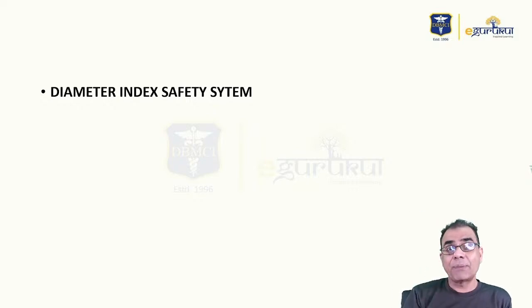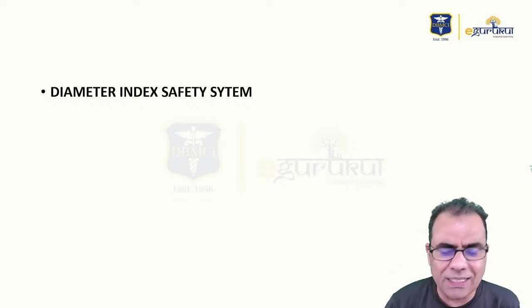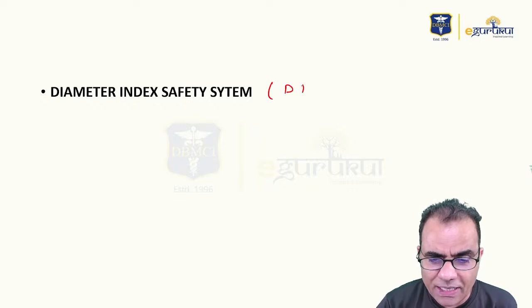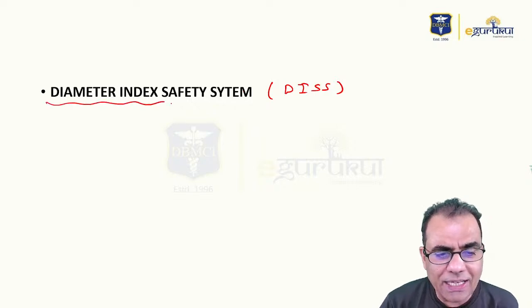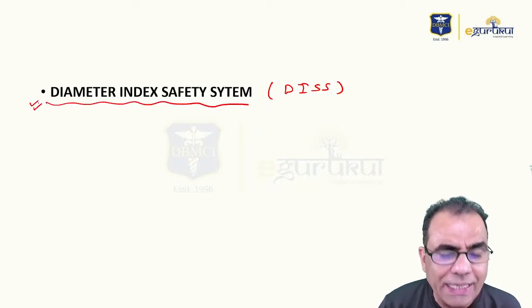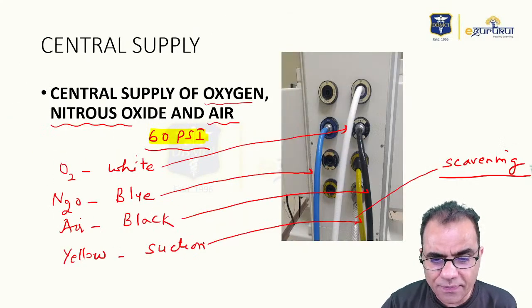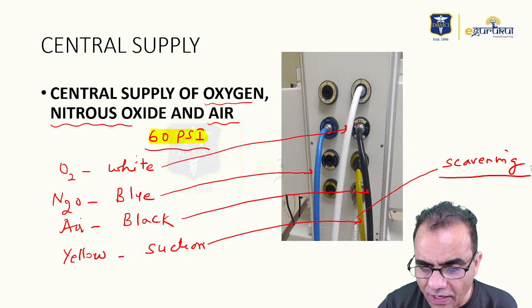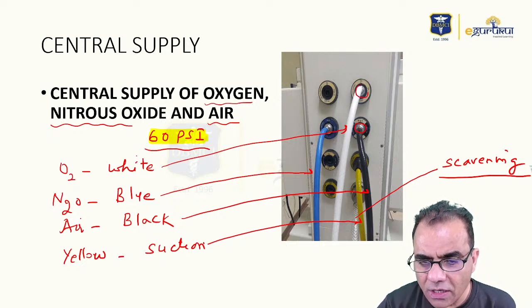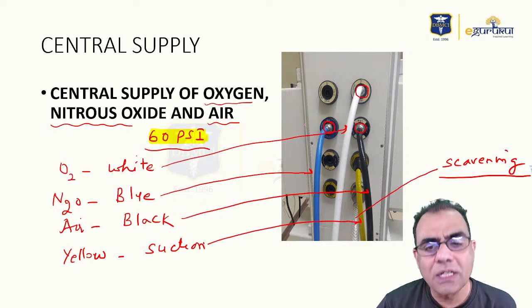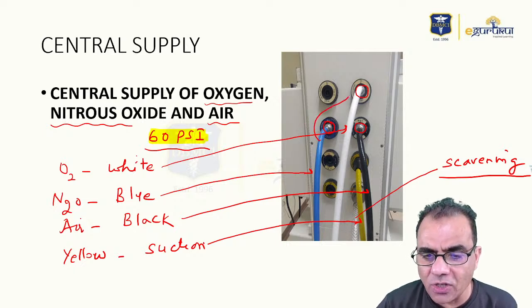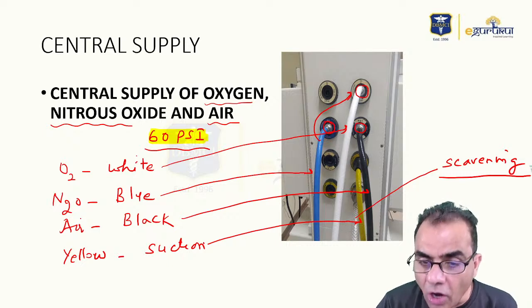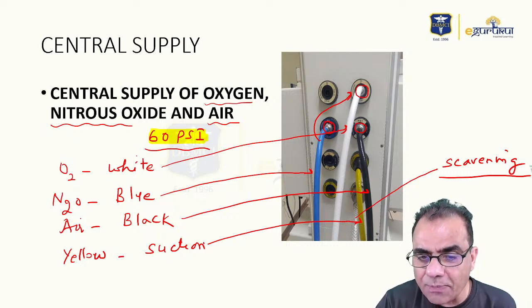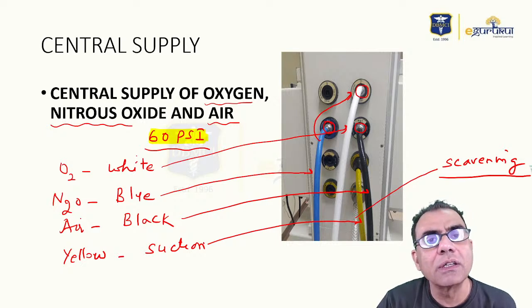Now, this is all we have discussed about avoiding wrong fitting of cylinders. Central supply pipelines can also get wrongly fitted. For that, the simplest system they have devised is the diameter index safety system, DISS. As the name suggests, there will be different diameters of these pipes. These pipes, where they attach in the slot, all have different diameters. That means if you try to place nitrous oxide at the place of oxygen, it will not fit, because the diameter of this pipe will not fit in the slot of oxygen.